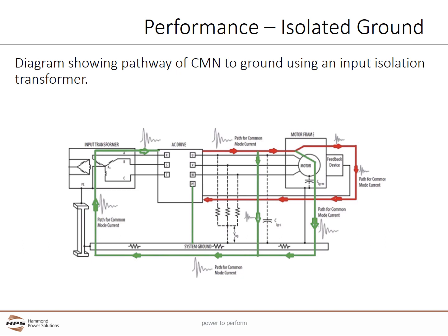Another nice benefit for using a dedicated drive isolation transformer for a VFD is the ability to ground out and remove common mode noise to ground. This circuit shows the path of the common mode noise to ground. Again, this is something that a line reactor will not be able to perform.